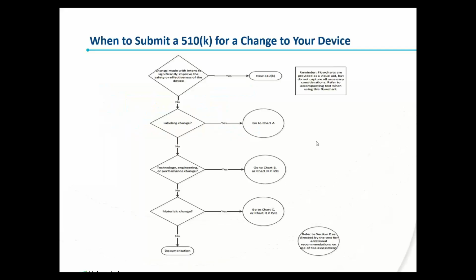So first up, I want to take a look at devices that have received FDA clearance under a 510K. These devices are under a lot less scrutiny than a Class 3 PMA device, and therefore have a much lower bar to get to the market with changes. First and foremost, I want to highlight that in this instance, we're going to be discussing devices that have maybe only had one or two other changes, or ideally none, since the originally cleared 510K. We're also assuming that each of these changes would have been minor and not previously required a new 510K.